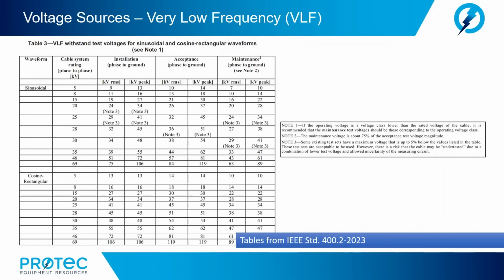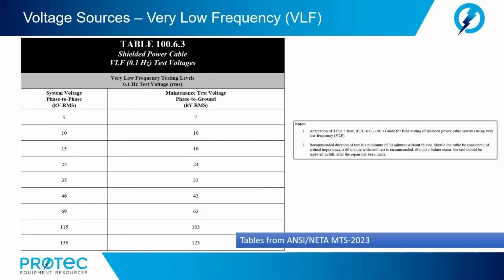Now, in the IEEE standard 400.2, 2023 revision, we can see the call-outs for VLF test voltages in Table 3, VLF withstand test voltages for sinusoidal and cosine rectangular waveforms. So again, in here we see whether we are using the cosine rectangular, what the recommended voltage levels are, or if we're using the sinusoidal, what the recommended voltage would be. Now, in the NETA material, we also see table 100.6.3. Now here, take special note that these are the voltages RMS for using VLF sinusoidal when testing in a field environment. So in table 100.6.3, we do see NETA calling out the use of 0.1 hertz test voltages.